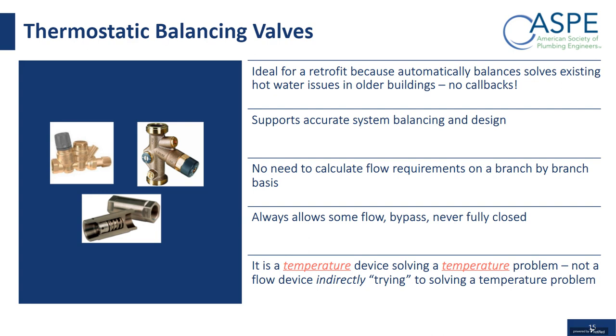So you don't have to worry as you would with a manual balancing valve or a pressure independent valve. You wouldn't have to know what flow rate you need in each of these branches or risers in the system. As long as the pump is sized properly, the valve will take care of itself. And as I already mentioned, these valves are always allowing some flow, some bypass. They're never fully closed. And again, for the second time now, these are temperature devices solving a temperature problem, not a flow device indirectly trying to solve a temperature problem.